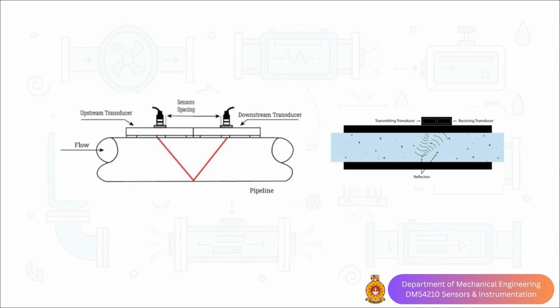There are two main flavors of this. On the left is the transit time method. It sends a sound pulse with the flow and another one against it. The pulse traveling downstream gets a little speed boost and arrives just a little bit faster. By measuring that tiny time difference, the sensor calculates the flow rate. This is perfect for clean liquids.